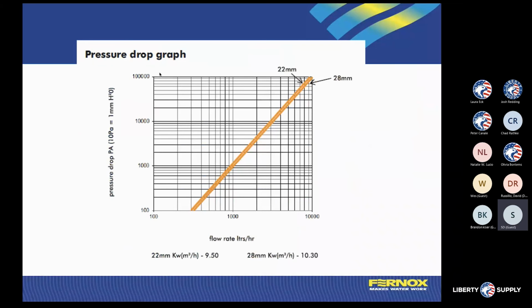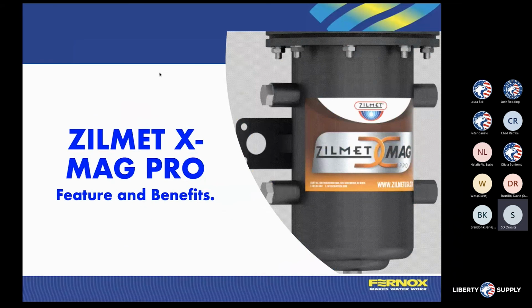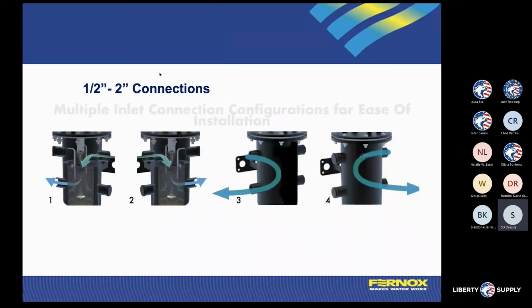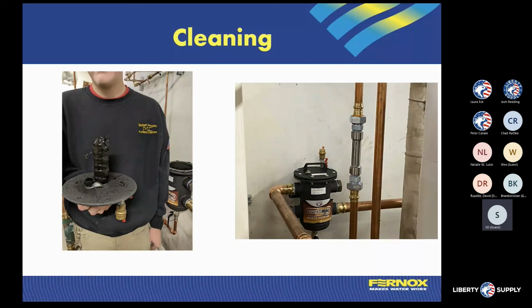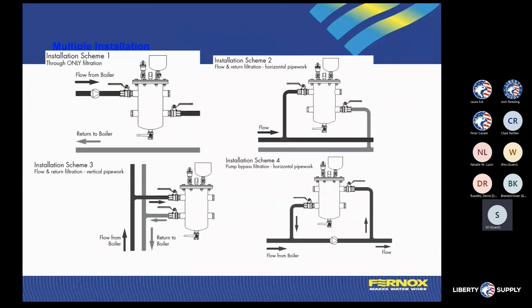Obviously, each model has a pressure drop, and that's how we get to sizing. On the Zilmet side, we'll talk about how we have a sizing guide for that. This is that 4-pipe X-Mag that we were talking about. This gives you a different installation operation so that we can have multiple piping arrangements, same side or cross patterns or anything of that nature. This is an installation that happened a couple weeks ago, where after the first 3 days, this is the sludge that was removed just by adding that magnetic filter to the process.